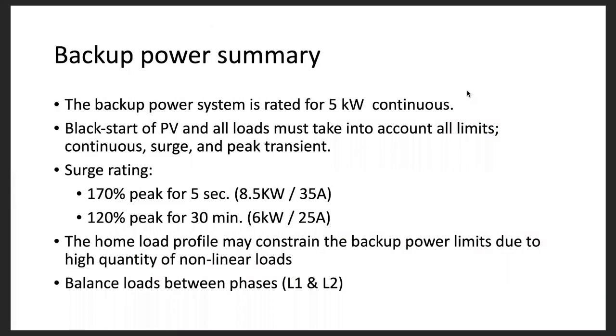So, backup power summary. The backup power system is rated for 5 kW continuous. Black start of PV and all loads must take into account all limits: continuous, surge, and peak transient. Because if those loads exceed the limits stated for the product when the grid goes down, customers who are expecting backup performance might just be tripping the battery off each time it tries to go into backup mode because there's an excess of loads on that backup loads panel. Again, surge ratings are listed here and on the data sheet, spec sheet. And the home load profile may constrain the backup power limits due to a high quantity of nonlinear loads.